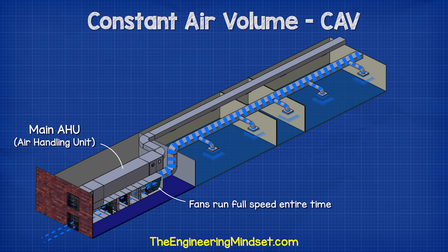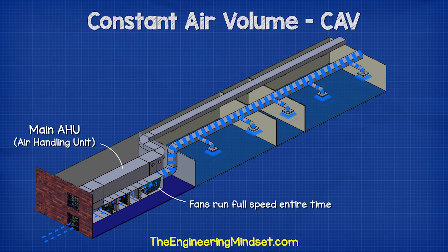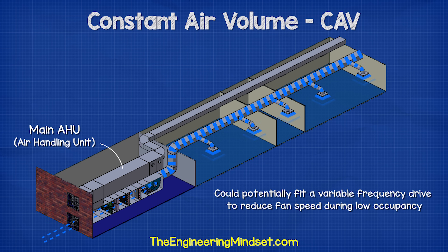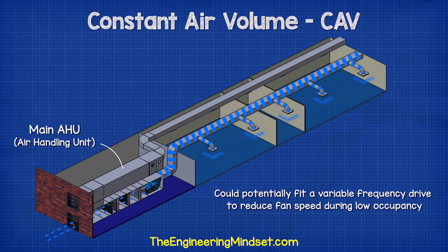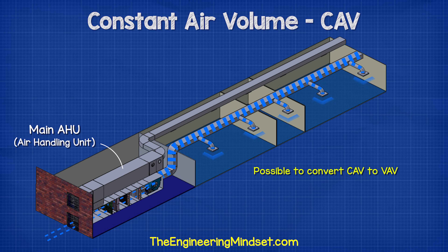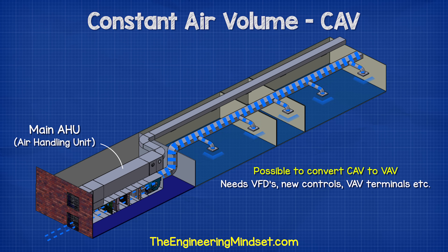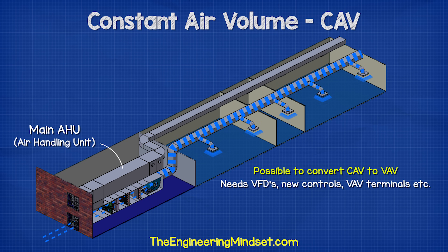The AHU fans will also run at 100% the entire time the system is running. Although you could fit a variable frequency drive to the fan motor and slightly reduce the flow rate at periods of low occupancy, keep in mind that this will impact how much fresh air is entering the room. Fitting just a VFD will not convert this system into a variable air volume system — we need a lot more controls, VAV terminals, etc. It does take a lot of time, money and effort to convert a system, but it can be done, although it might not be economical depending on the size of the building and the lifespan of both the equipment and the building.